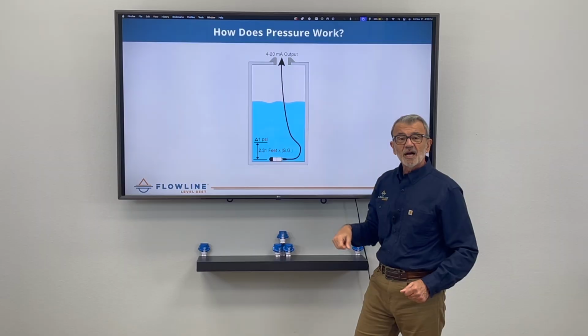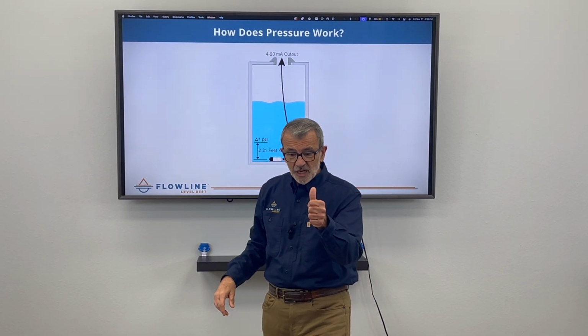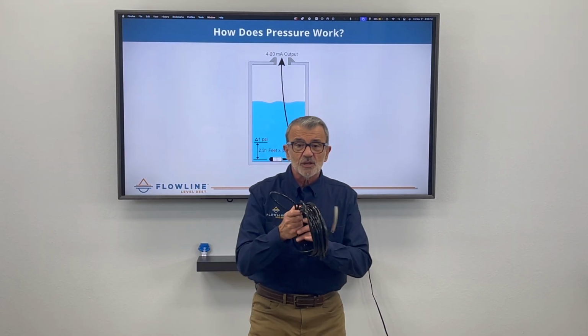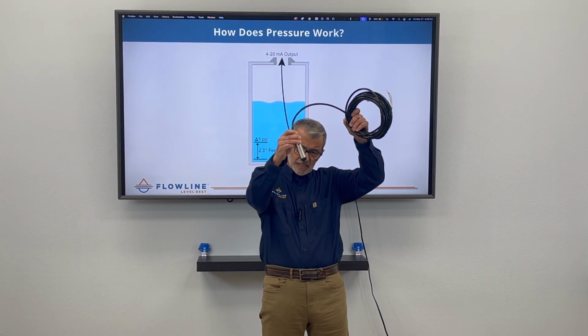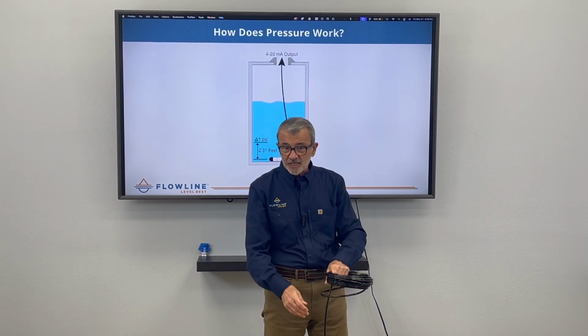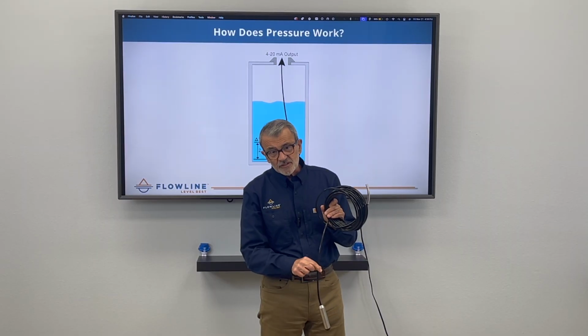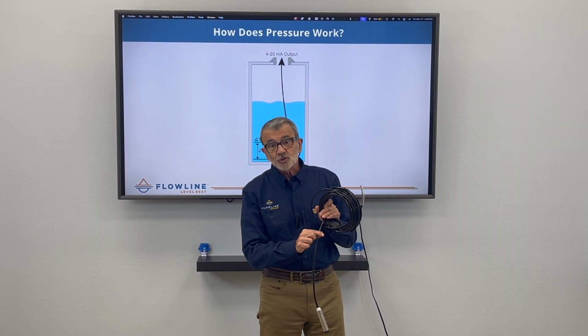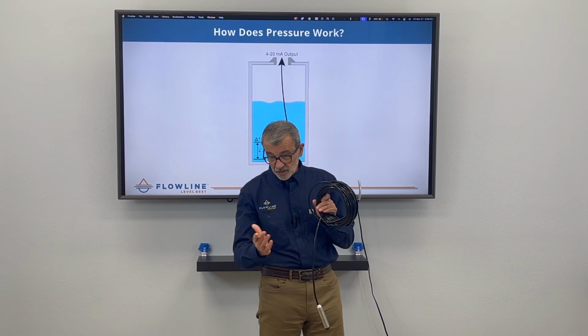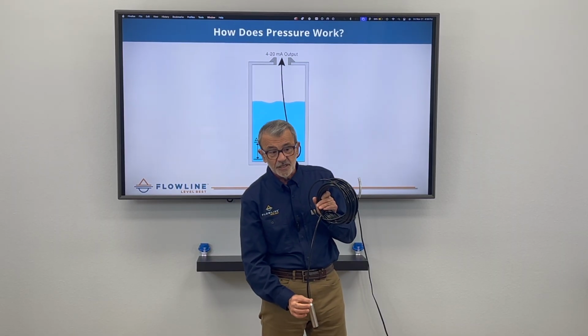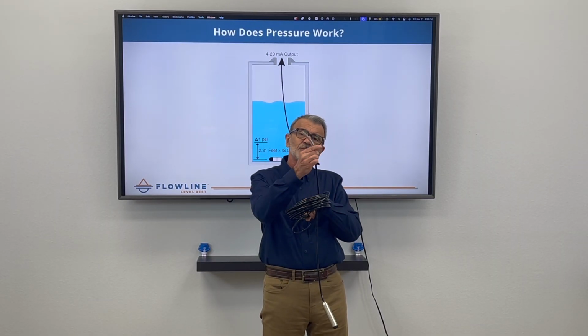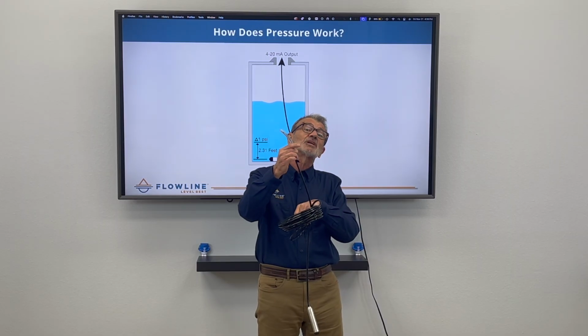It's done a couple of different ways. One is what you see in this diagram, which we call the submersible version. You actually have a sensor element, a pressure sensor element, that has to drop down to the bottom, and you need a specialty cable that is corrosion resistant because it could come in contact with the liquid, fully sealed here, with the end that outputs a 4 to 20 milliamp signal outside your tank.